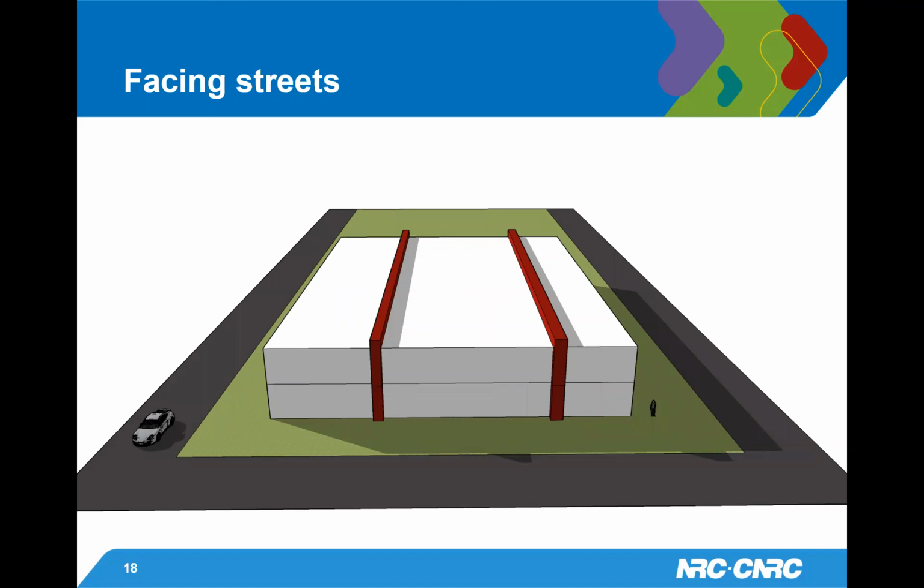This diagram represents 3 buildings separated by firewall construction so that they are considered as 3 separate buildings. To allow access for firefighters to the building perimeters that would be acceptable for them in response to a fire emergency, mid-rise combustible buildings containing Group C and Group D major occupancies require that not less than 25% of the building perimeter be within 15 meters of a street or streets.